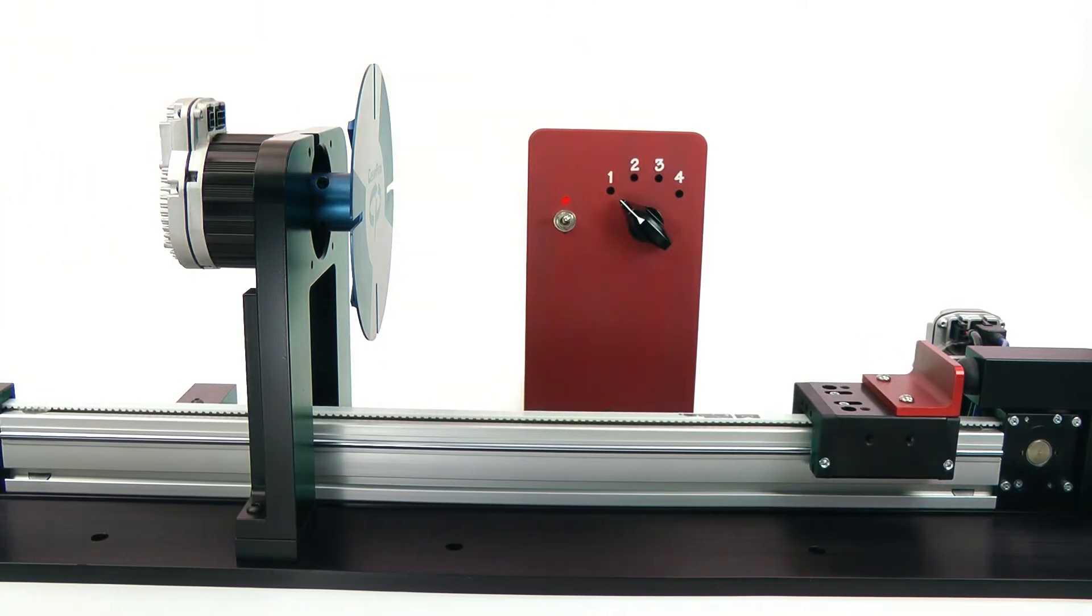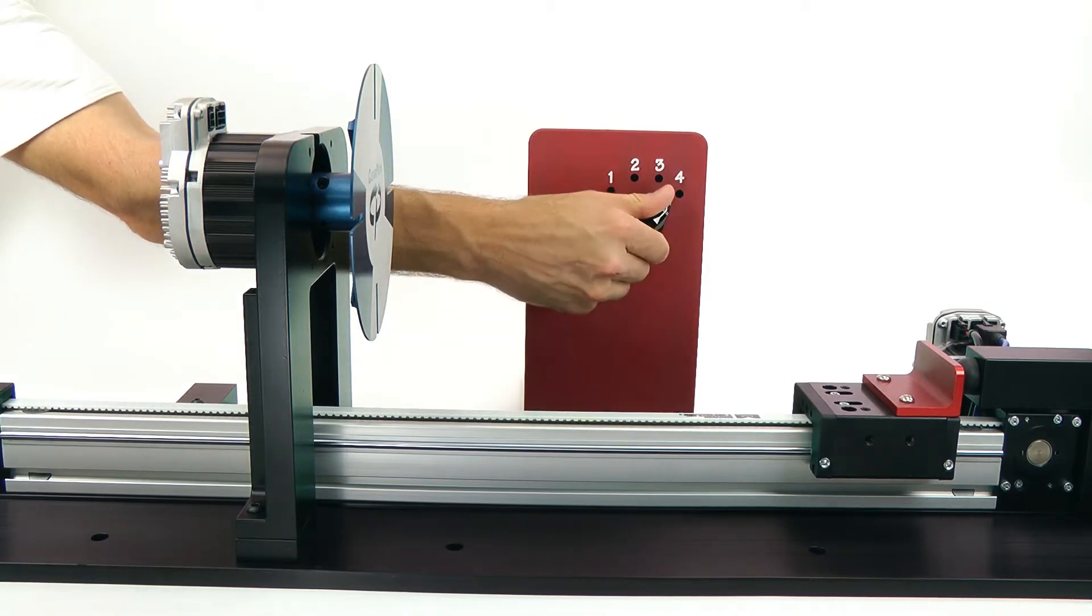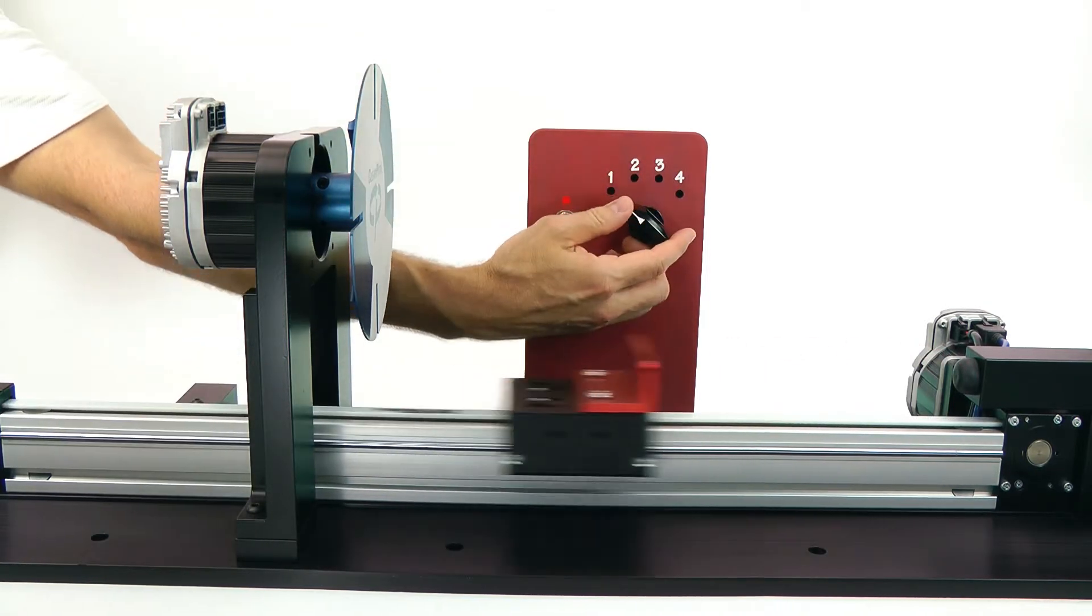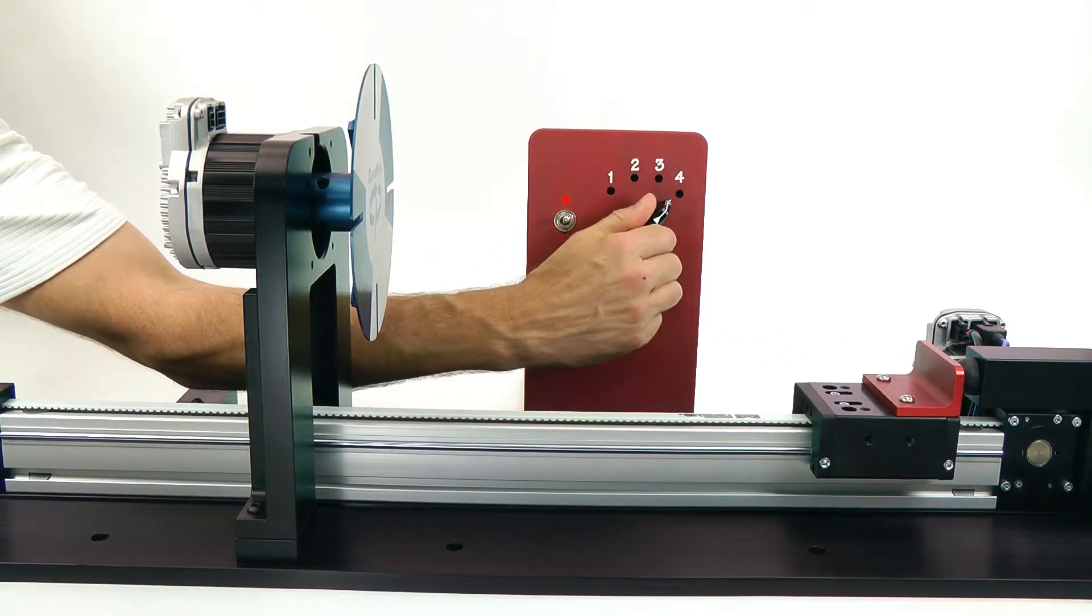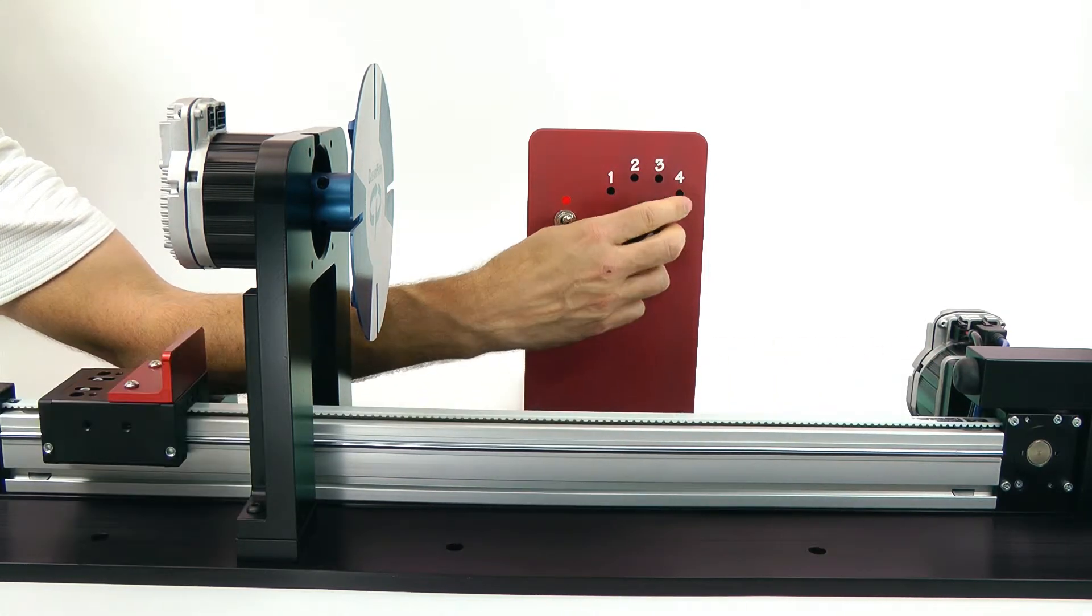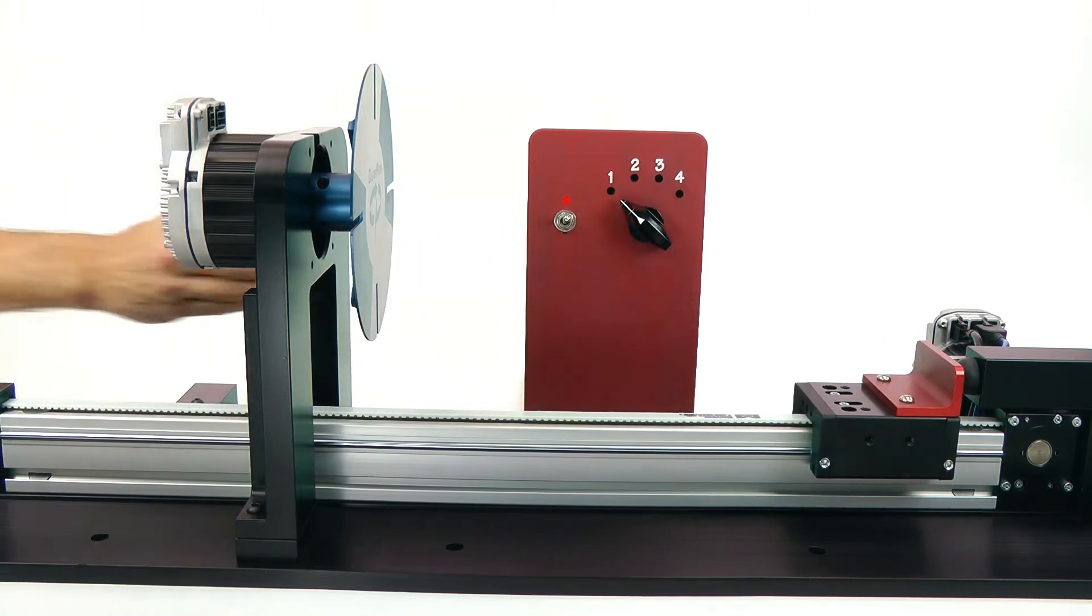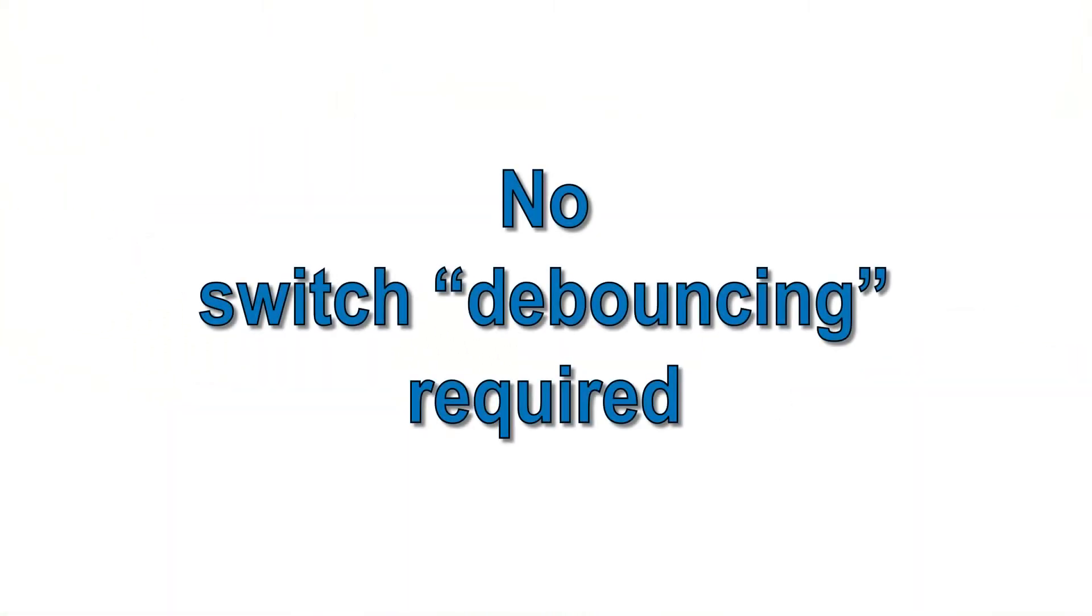You may have noticed that I can switch through intermediate states like going from position 1 to position 4 without any glitches. This is because ClearPath has an adjustable input filter that allows time for the inputs to stabilize before any motion begins. This also means you don't have to worry about mechanical switch bounce.